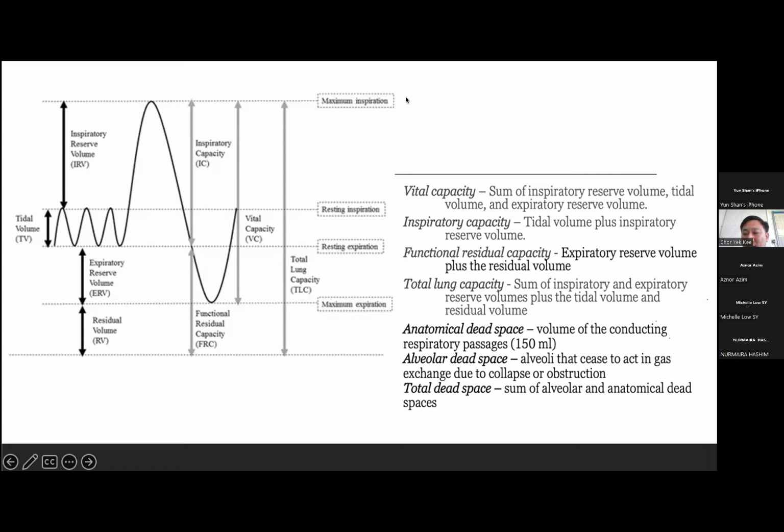Dr. Cho, Myra here. I just want to re-clarify about this compensation thing. The compensation for the tubing on the ventilator. Some ventilators have the option of tube compensation on, tube compensation off. So meaning you should compensate for the tubing, am I right? Yes, please compensate. You have to compensate the compliance, then only you can have accurate tidal volume measurement. All right, okay, thank you.